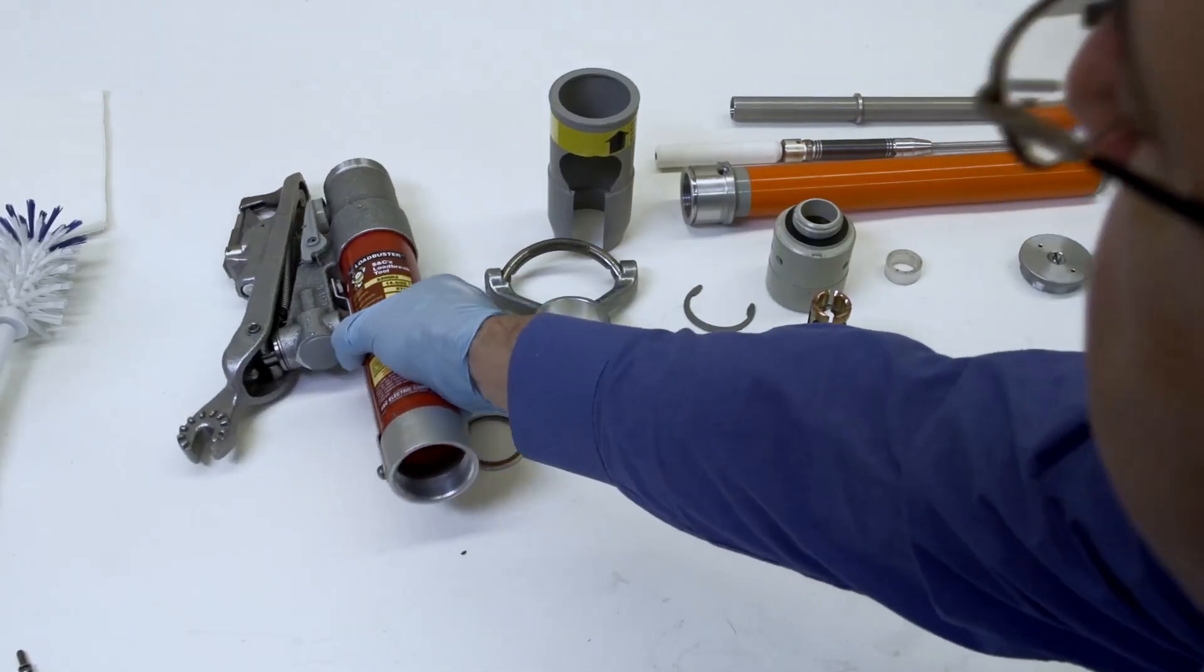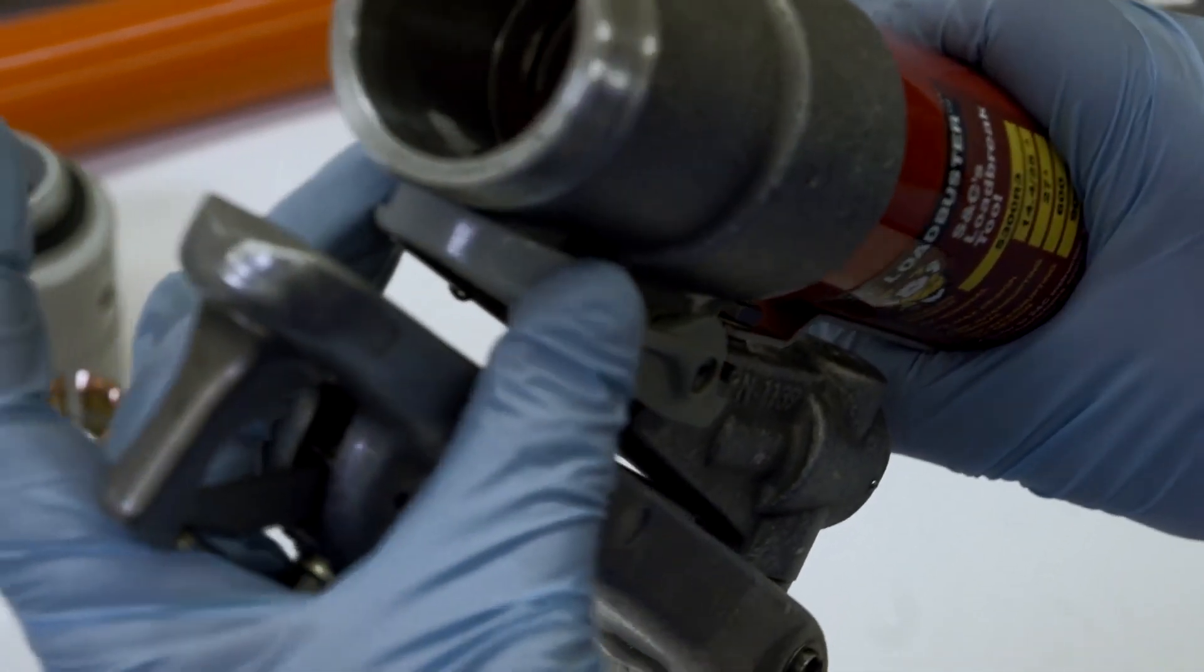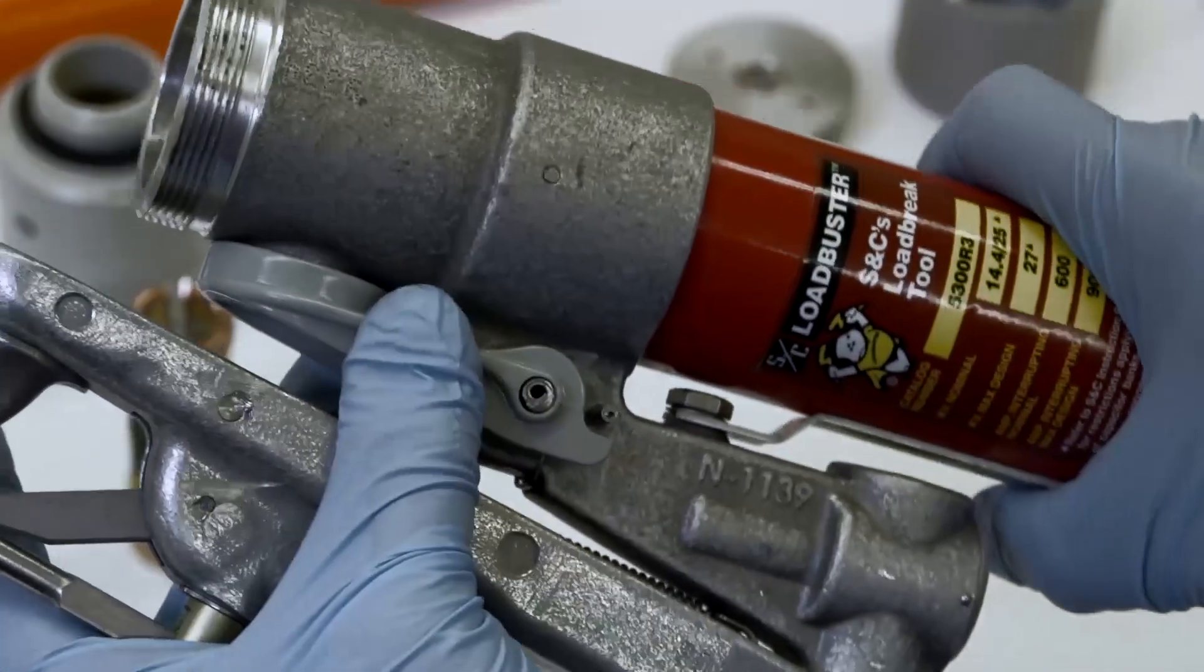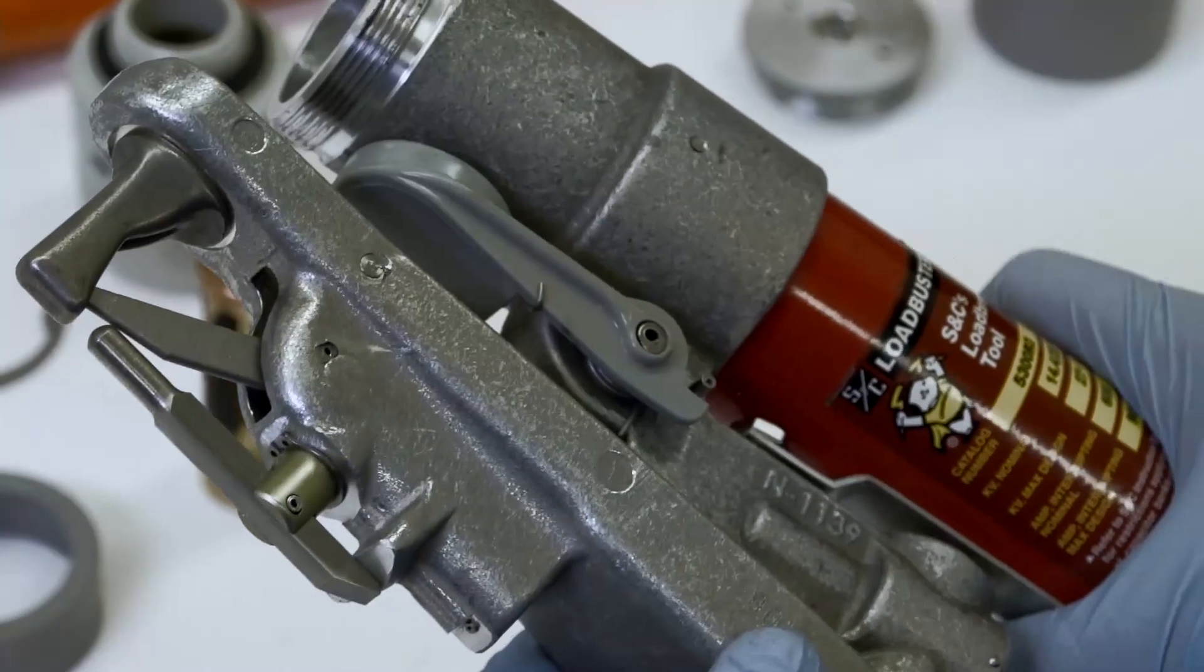Next we'll look at the latch and hook frame assembly. Examine the latch and look for excessive wear on the latching surface. The surface should be flat. Check that the latch's spring action is in good working order. Replace the latch if it is damaged.